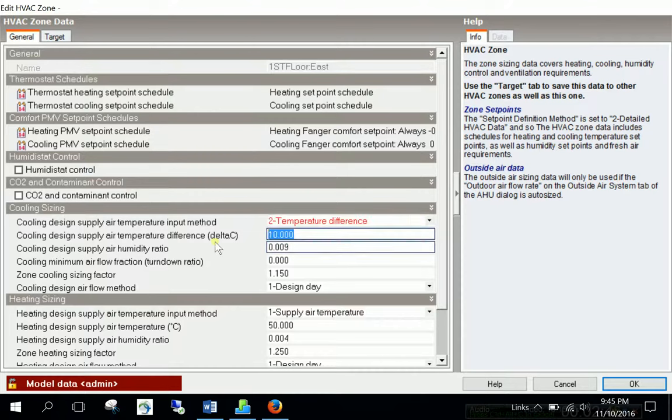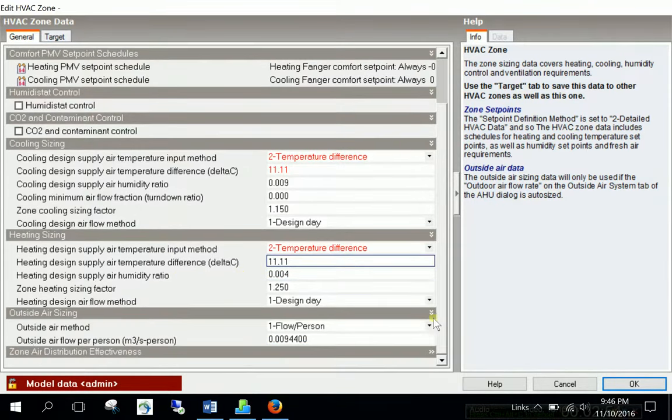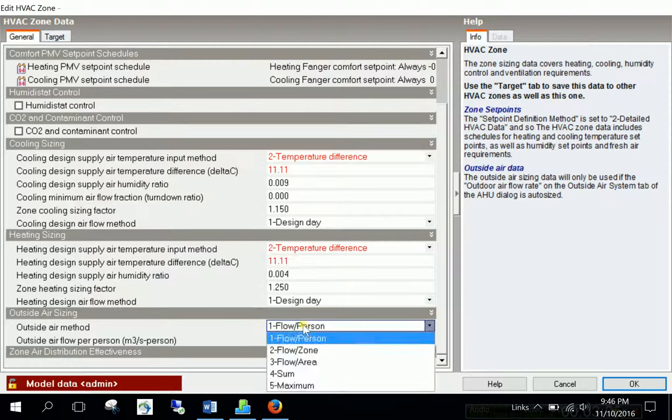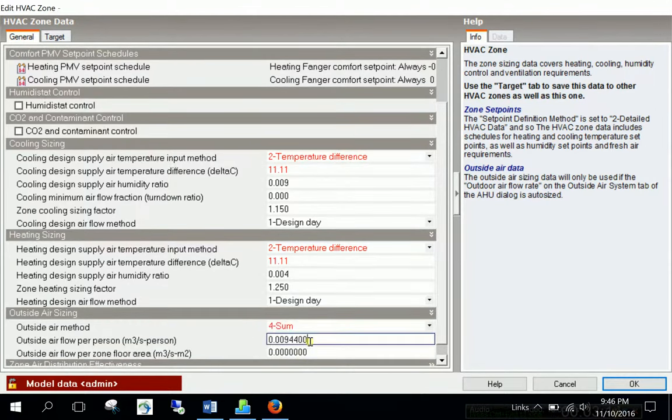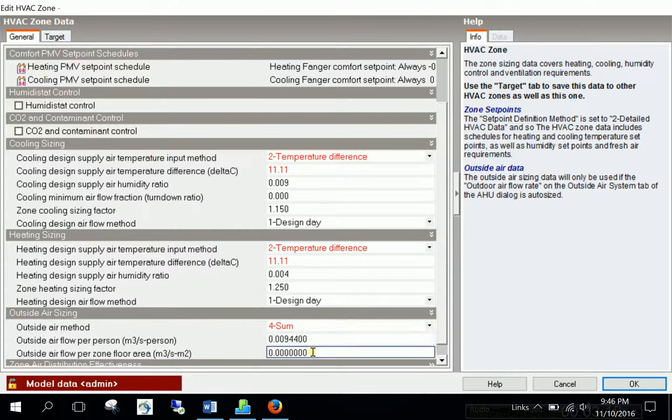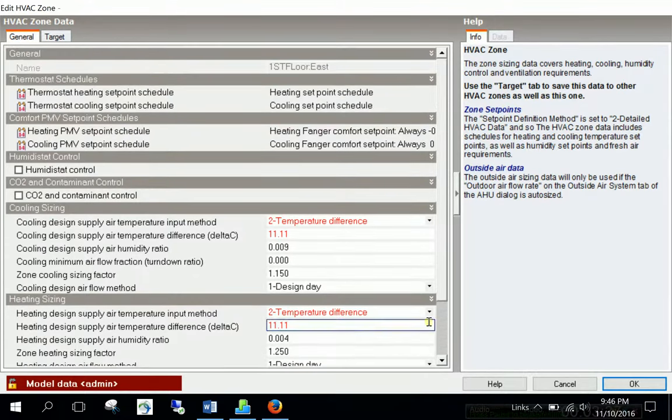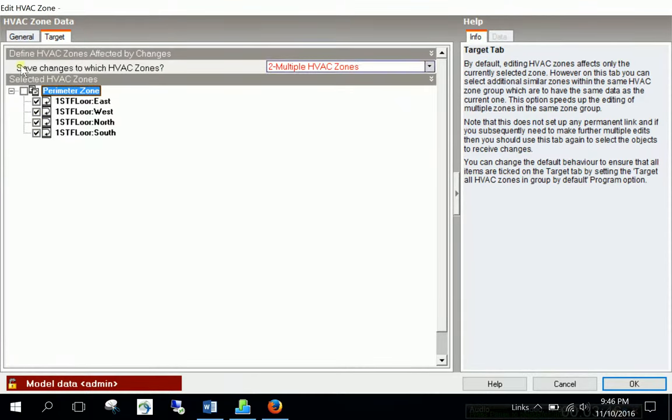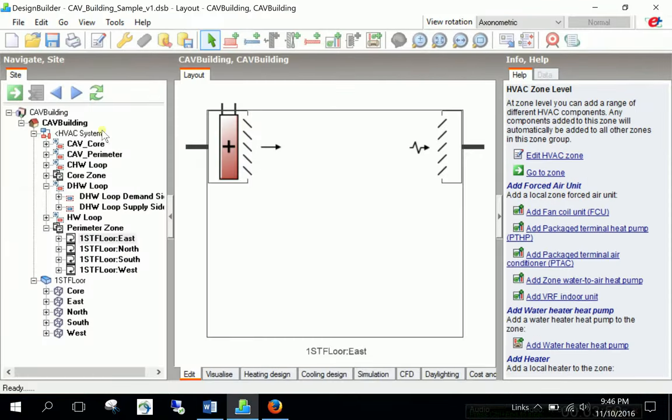It is within the same operational hourly schedule. You don't need to change or have a look at the comfort PMV. You don't need to use humidity setpoint control, humidification or dehumidification. No CO2 based control. But you can change this cooling sizing supply temperature to temperature difference and set it to 11.11. And do the same for the heating. Change it to temperature difference, 11.11. These are for cooling and heating sizing setups. And how about outdoor air sizing? Very important. And we are discussing this in our lectures again and again. Find the information from the relevant standards. Basically, ASHRAE 62.1 or ASHRAE 62.2. And then find the sum method and find the values for flow rate per person, flow rate per zone area. And put them in here. Of course, these are meter cube per second per person or meter cube per second per meter square units. So if you find some unit in CFM per person or CFM per feet square, please make the right changes. Remember the target. If you want to apply these changes to multiple zones, you should select the zones that you want the changes to be applied and say okay. And the changes apply.